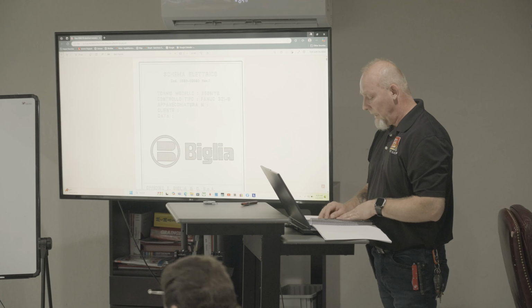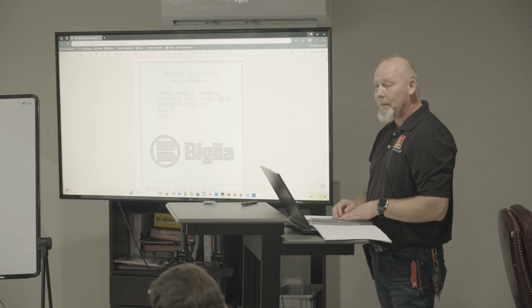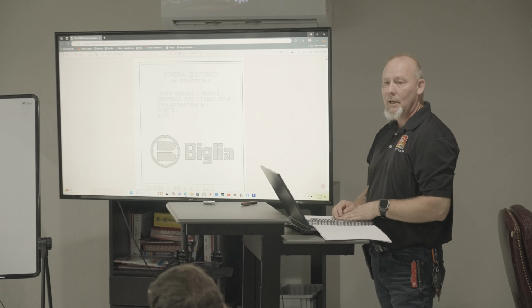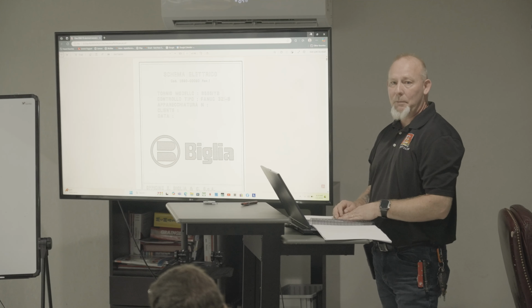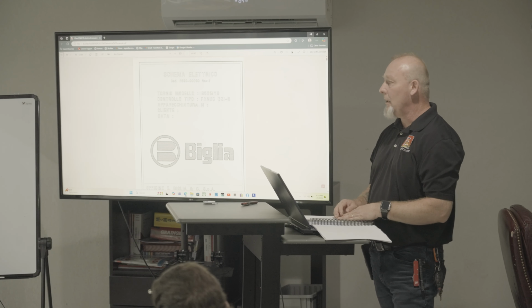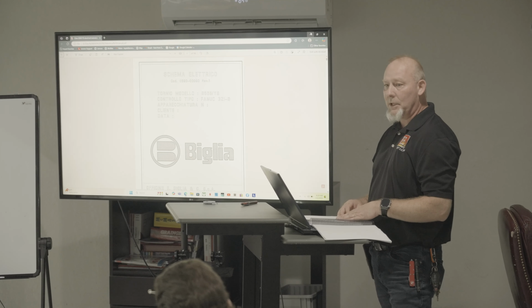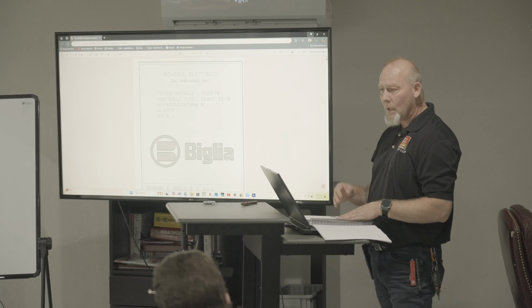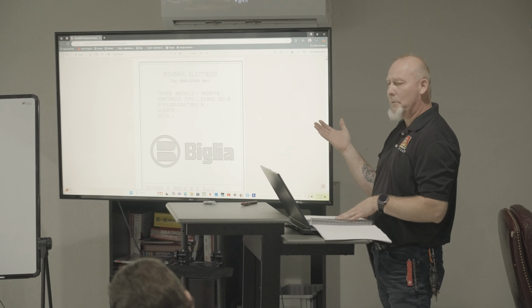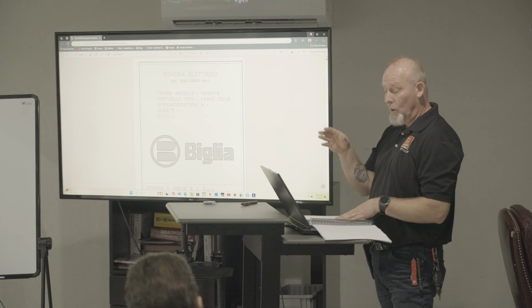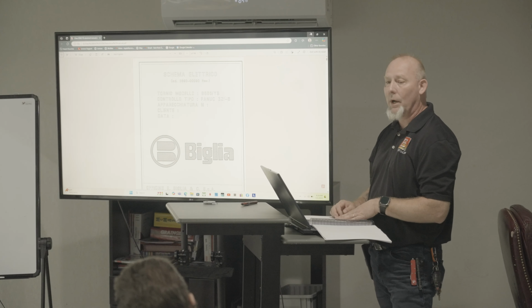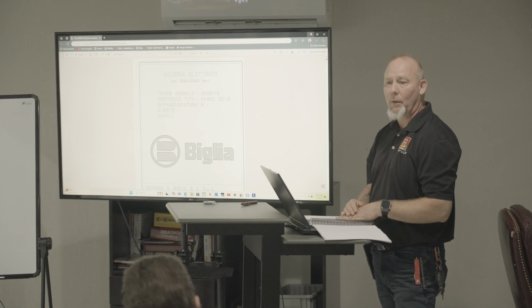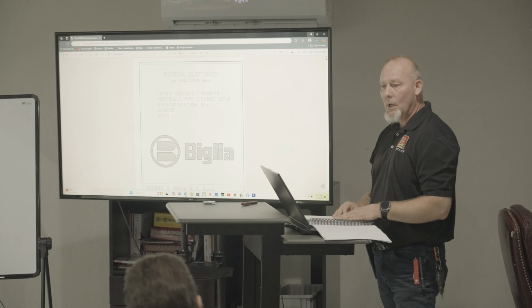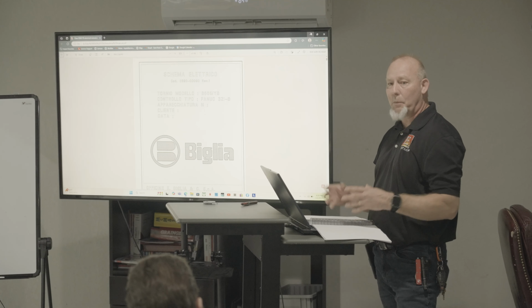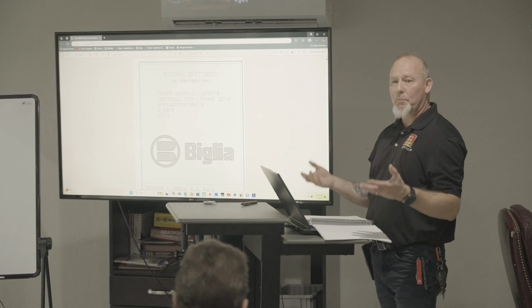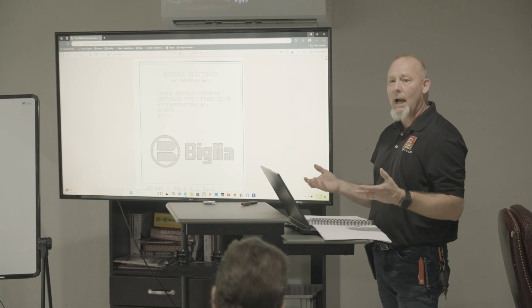So you have the K7. The K7 is a coil that's on that main disconnect, and that's for our auto shutoff. Typically, at the end of the day, if you shut your machines down, or your customer shuts the machines down, we recommend that they just push the e-stop button in and walk away. There's a timer in there set for about 8 to 10 minutes, so the machine will release that coil, trip, and kick out the main power. This way the machine just shuts down on its own. The reason they do that is because they have air purges on the main spindle and the sub spindle, and they want it to purge out any remaining coolant before you shut down.